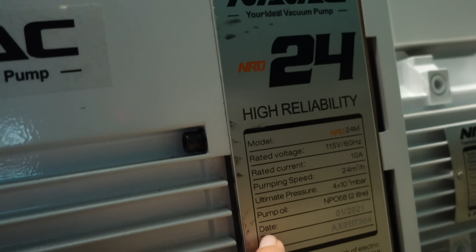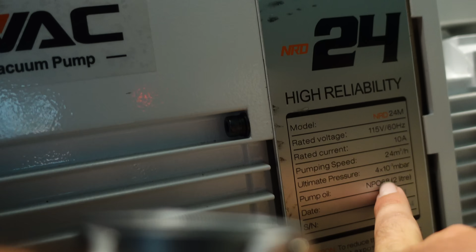At least that's been my practice up to this point. Their recommendation is, before each vacuum starts, see if the oil that's in there will still pull the pump down to its specification. For example, this pump is able to pull down to an ultimate pressure of 4 times 10 to the -3 mbar, whatever that means converted over to microns—that's what they want you to use as a baseline test.